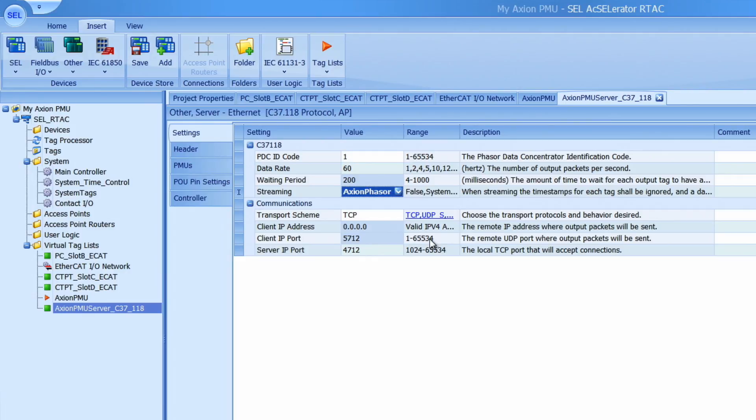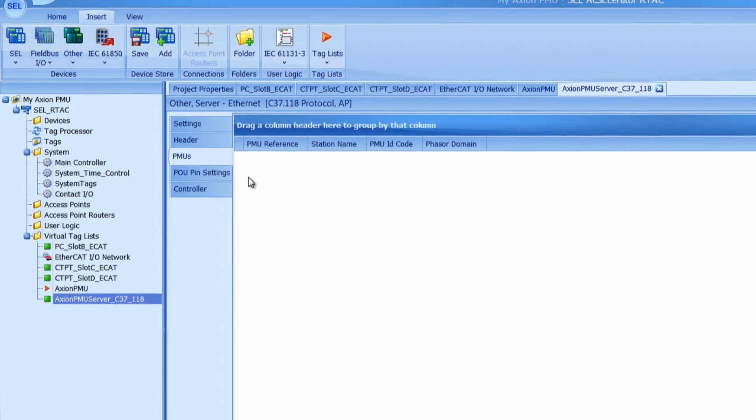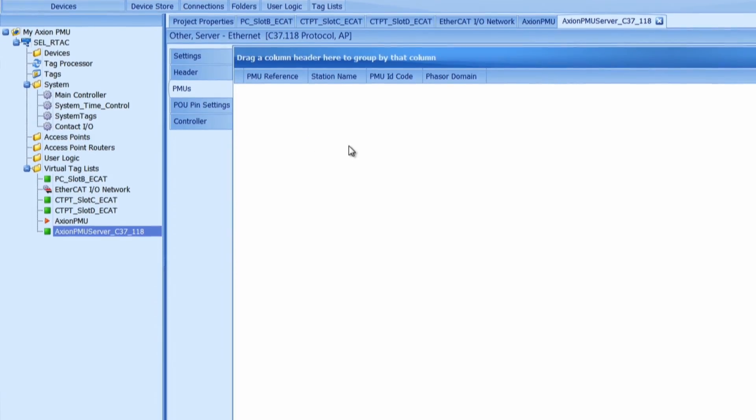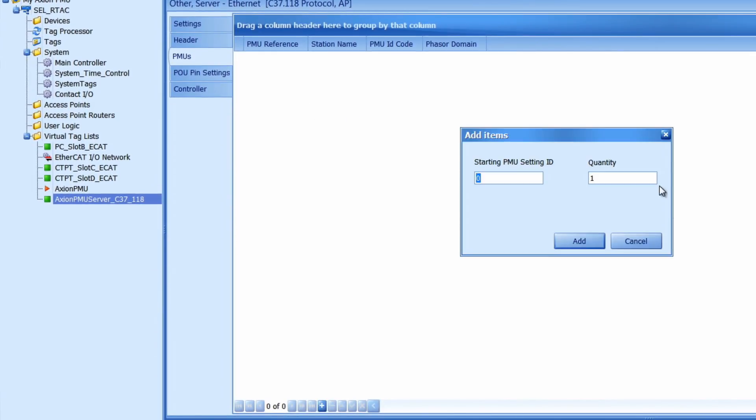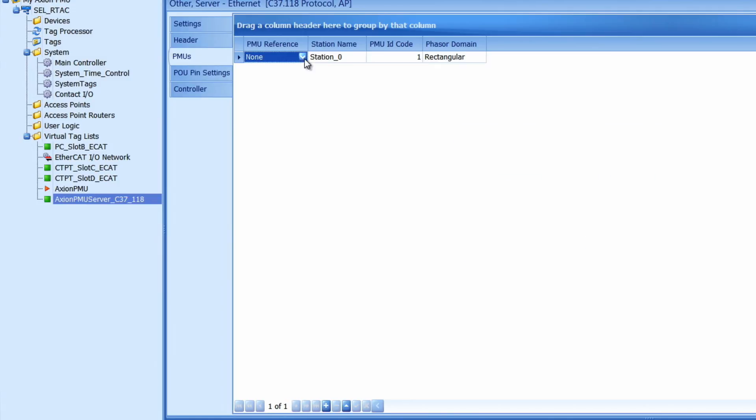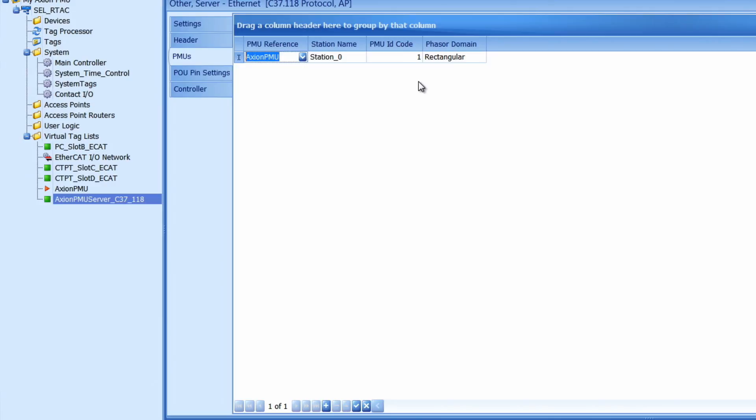The last thing we have to do for configuring this server is go to the PMU tab and add in our PMU. I can click on the add button down here and add one PMU to the system. Then I will add the PMU reference which is the virtual tag we just created in the previous step. And I'm going to change the phaser domain to polar because that's what I prefer for this application. You are welcome to change these parameters as you wish.